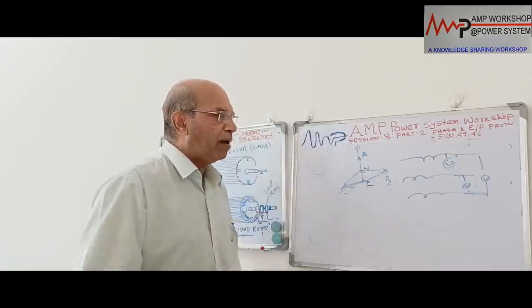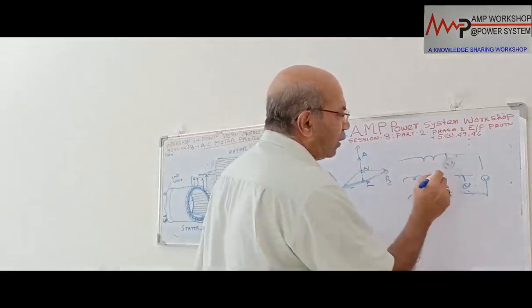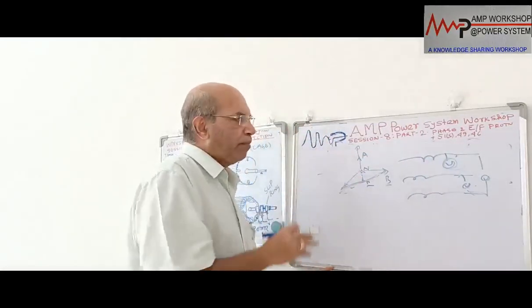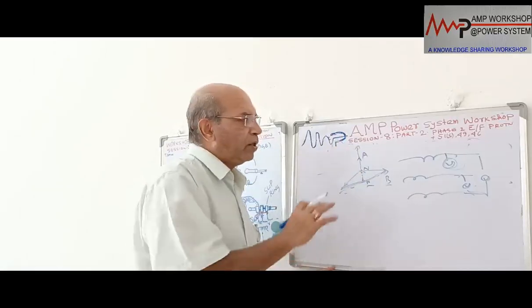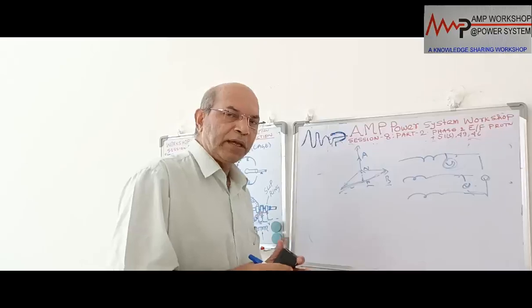At least we can give an alarm when there is a fault. Immediately the phase voltage will become the line voltage. The maximum voltage can depend on the earthing factor. So the maximum value can go up to the line voltage. So by measuring the phase voltage, we can protect the motor from the ground fault also.